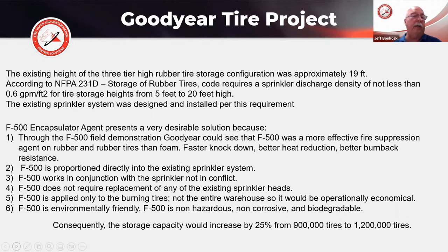So testing was done, looking for a better fire protection solution, testing foams and F500. They found that by adding F500 into the system, they could go that additional rack higher and keep the sprinkler density at 0.6 gallons per minute per square foot. They were able to keep that density, add F500, and go one rack higher. They found that use was actually better than reducing the sprinkler density and adding a high expansion foam system.